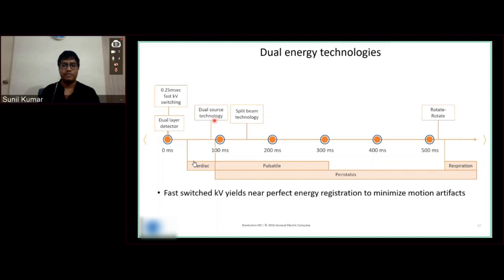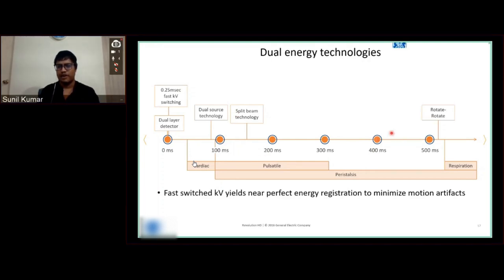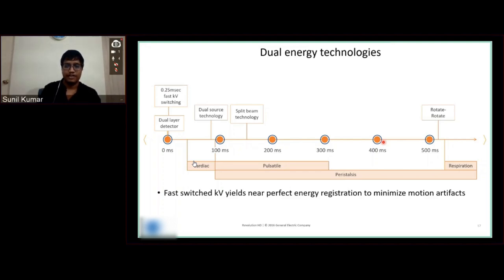Cardiac GSI is possible only with GE's fast kV switching method — no other vendor has cardiac GSI. For split beam, it is over 140 milliseconds. For rotate-rotate, it is far away — more than 500 milliseconds. To conclude, we need perfectly registered energy data of two energies, which will enable us to get GSI-based images and minimize motion artifacts.